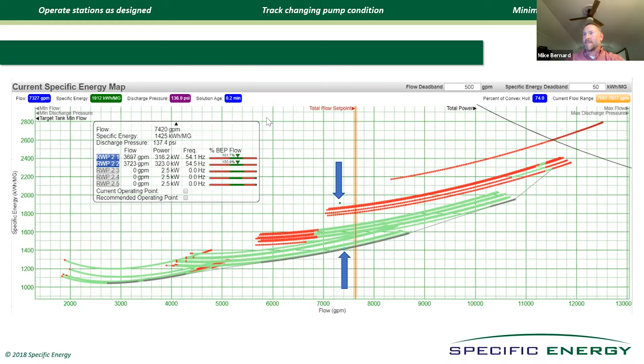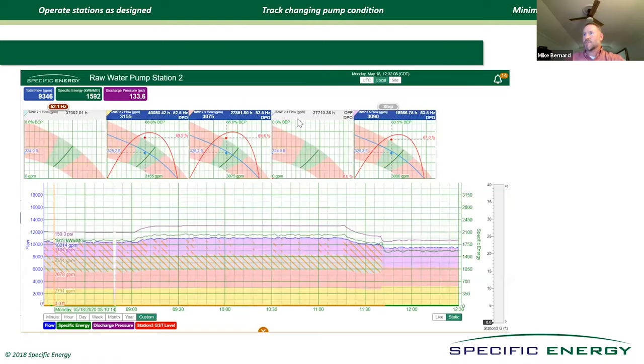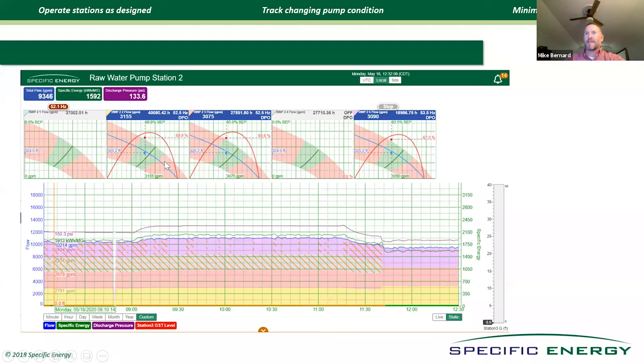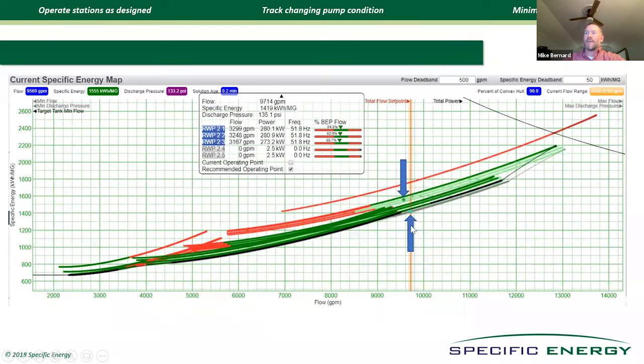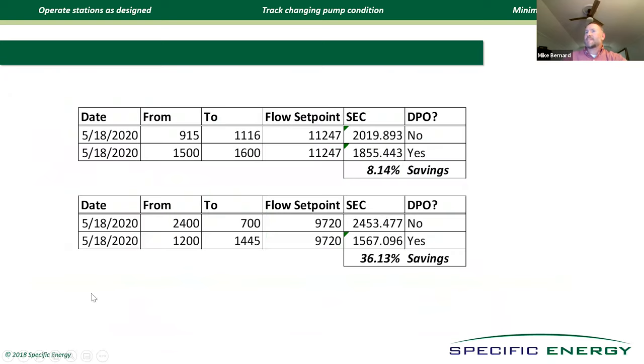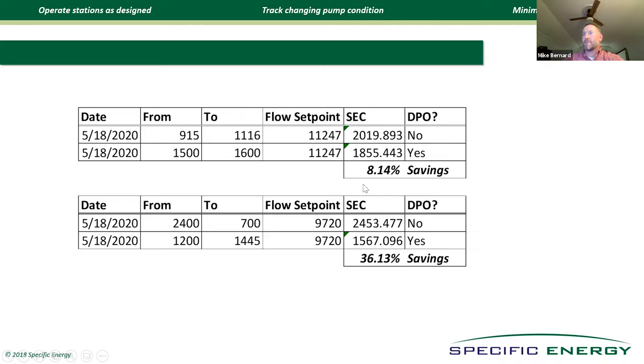About an hour later, I get a phone call from Casey Bloat at GBRA. And he said, hey, I'm a new treatment plant manager here at San Marcos. And I'd kind of like to know how the hell you know that about my pump station. And so I took him on the same tour that I just took you. And he said, you're telling me that I have access to this? So I created him an account and he looked at it and said, I want to do it. Let's put it in DPO mode. So we did that. As soon as the DPO was enabled, it turned off pump four because it was the least efficient pump. It sped the other pumps up. It really is that simple. If you're on the left side, you need to speed up. If you're on the right side, you need to slow down, just like your tachometer.